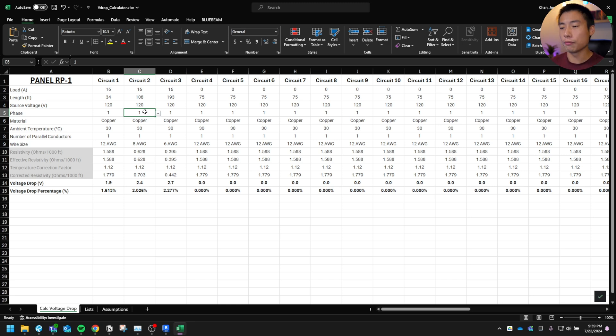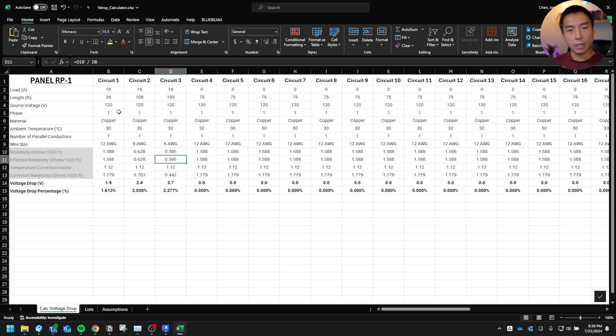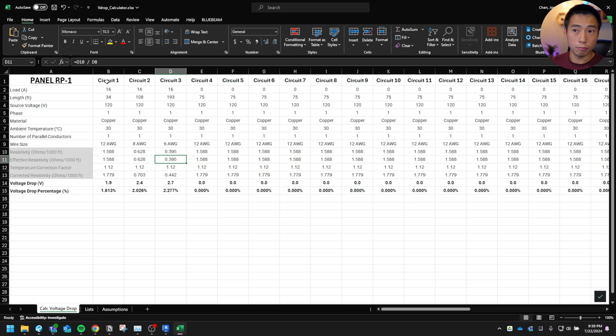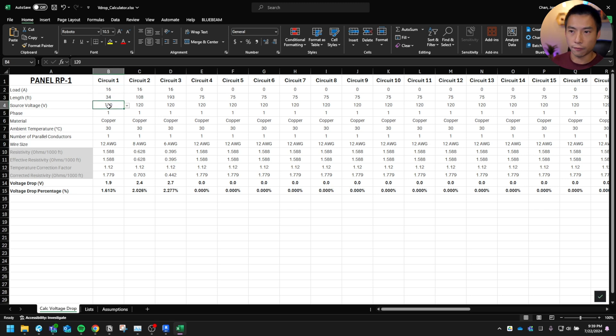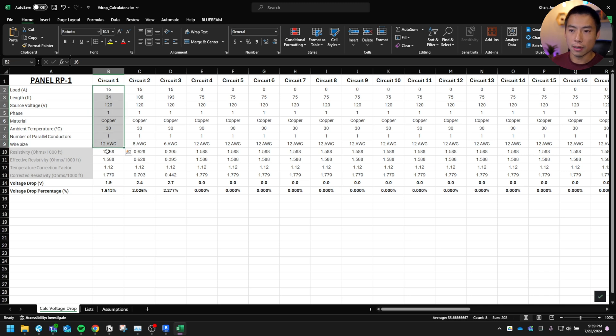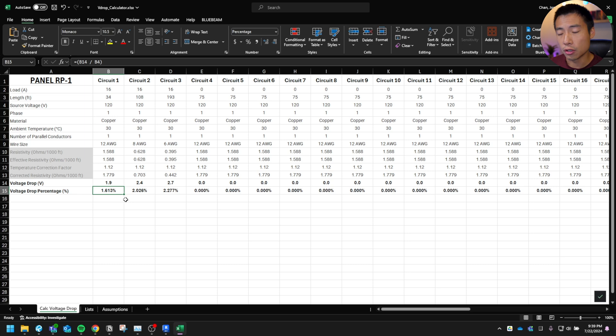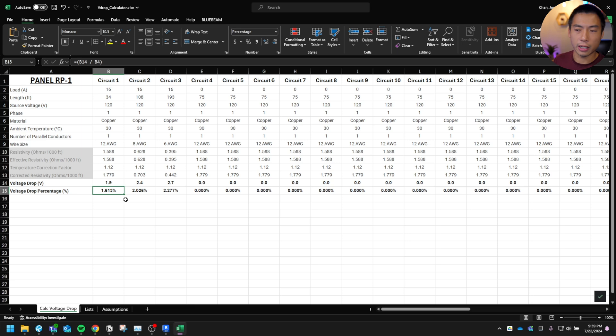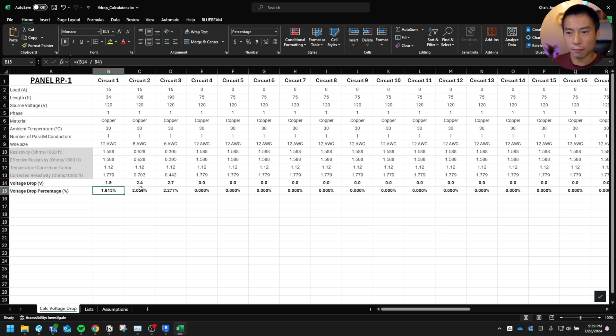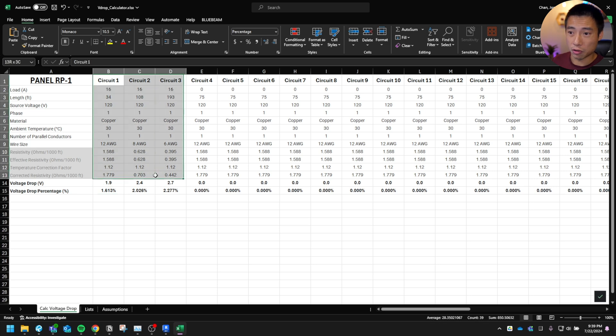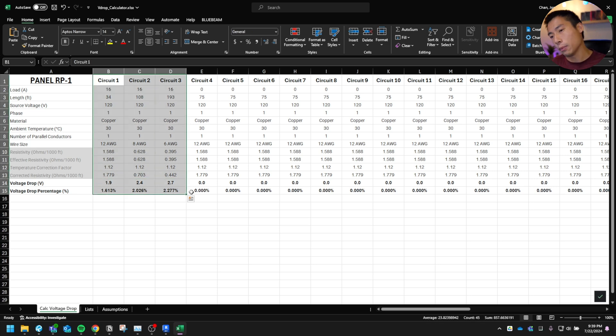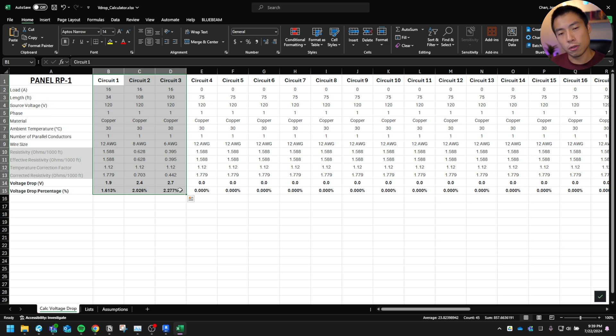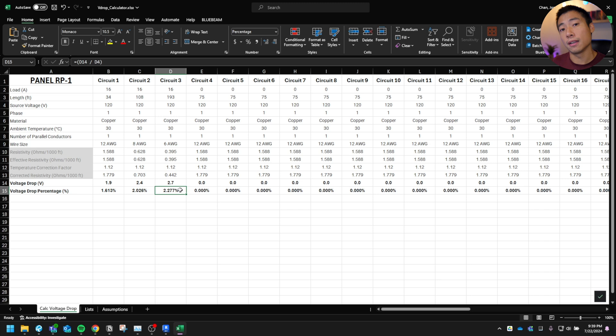Before we dive in, I just want to say that this spreadsheet I use does a pretty decent job at calculating voltage drop manually. So if you know your amperage that you're going to pull plus your length, your phase, yada yada, you can punch it in up here and it'll do the math and spit out a voltage drop percentage. So typically I try to aim for 2% on the feeder, 3% on the branch circuiting, total 5%. You can grab a copy of this spreadsheet if you want, I'll put a link in the description. It'll probably be like a Google Drive download.